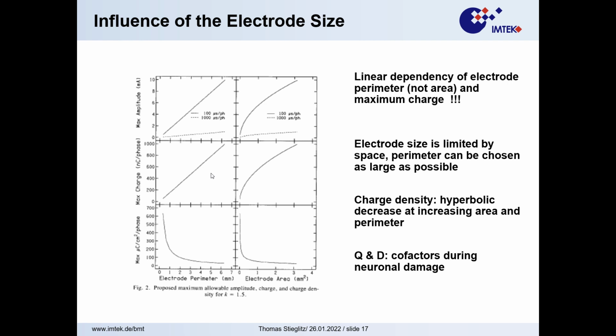in most cases, the electrodes are quite large for safety reasons, and your need of selectivity is relatively low. That means you're twice on the safe side if you make the electrodes larger. And in the other cases where you need high spatial resolution, then you could play around, but sometimes manufacturing limitations determine the shape. They say, okay, if I have to weigh this advantage versus that disadvantage, I'll go that way, and this quite often simple shapes.